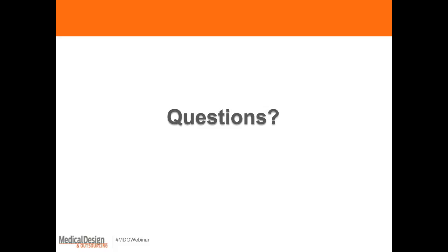The guidance that I referenced earlier is a good place to look to determine whether or not your software change is going to require that submission of the 510K. It may be a simple enough change, let's say just in the graphical appearance of the user interface, such that no other factors are affected, and you may be able to do a letter to file. But once again, you have to do the assessment and look over not only the guidance on when to file a 510K for a change in device, but also the FDA's guidance on software validation and their expectations there.